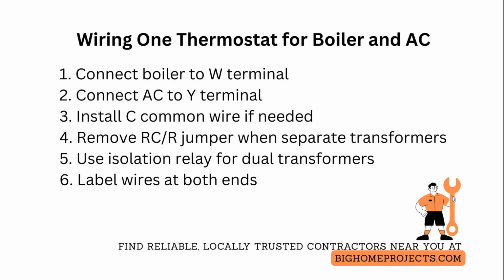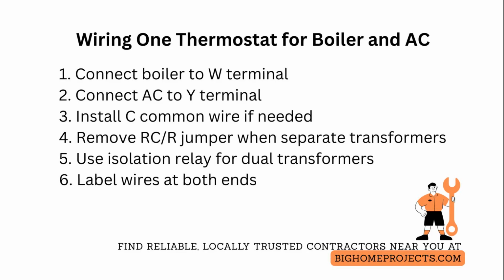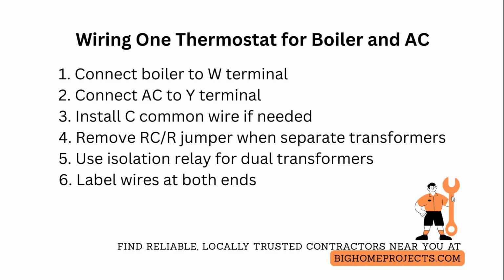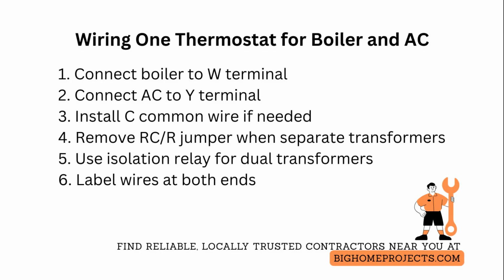If the thermostat must energize 2 separate transformer circuits, install a relay or an isolation module at the control board so only one transformer is driving the thermostat electronics and the other system is switched by the relay contacts. Choose low coil current relays rated for 24 volt control circuits.